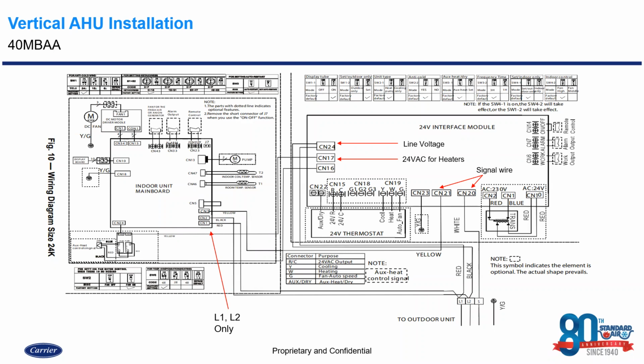So in this configuration for a 40MBAA, your dip switch settings for SW11 and 12: SW11 should be on to allow the display to come on, and SW12 with the 40MBAA should also be on to indicate that we have a true ductless indoor unit, ductless outdoor unit paired with this 24-volt interface.